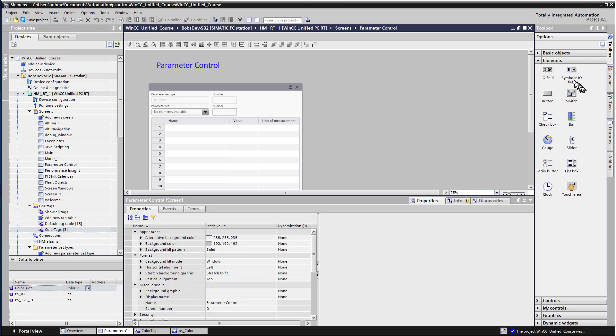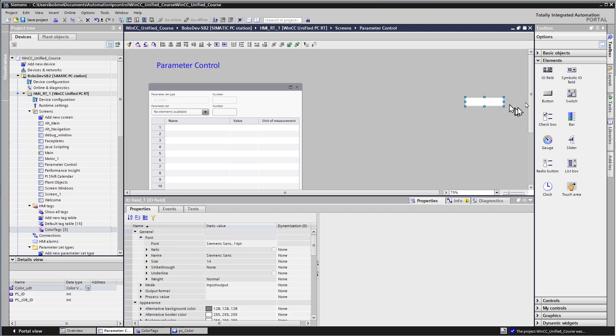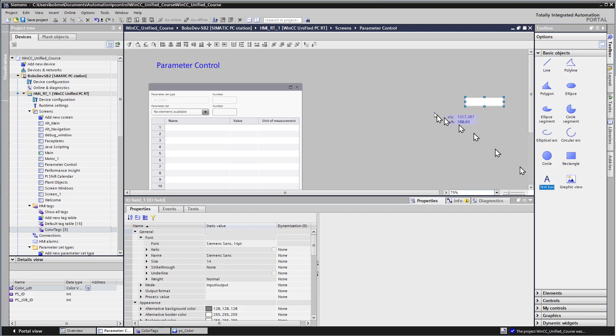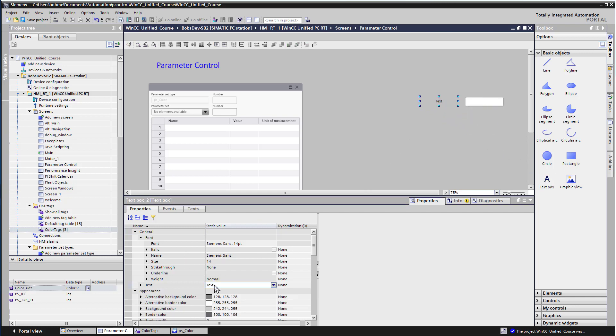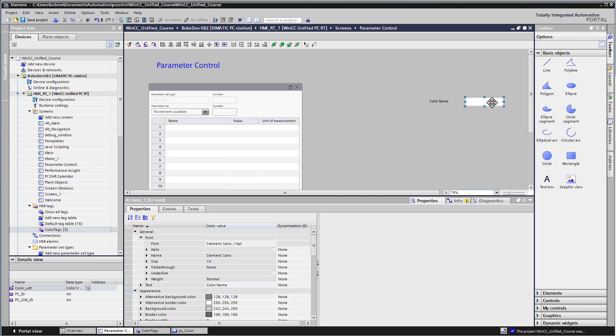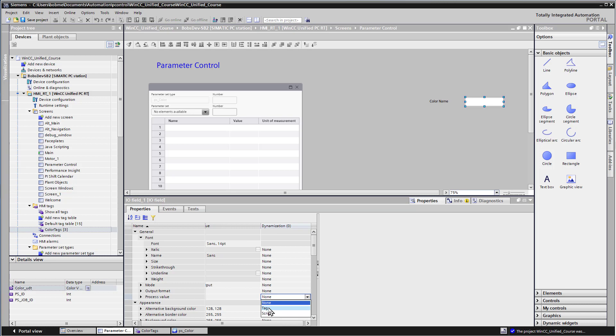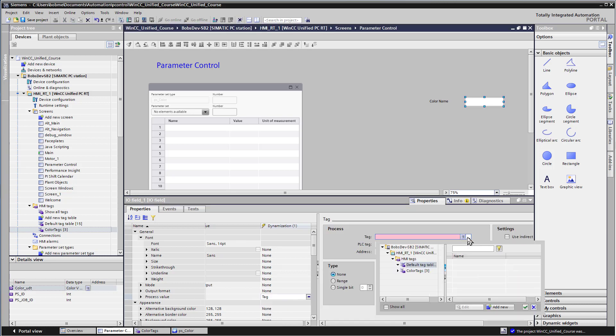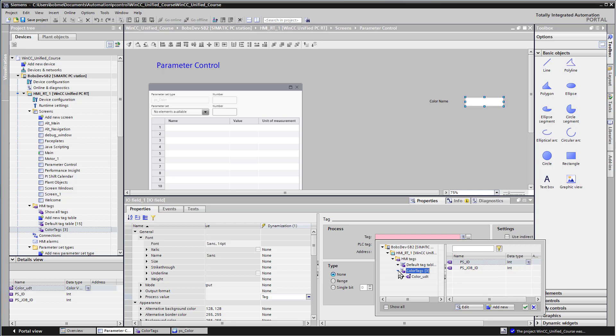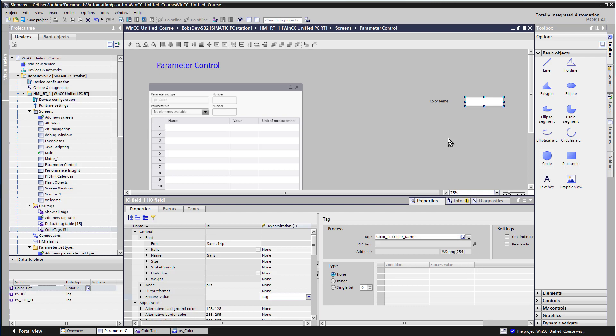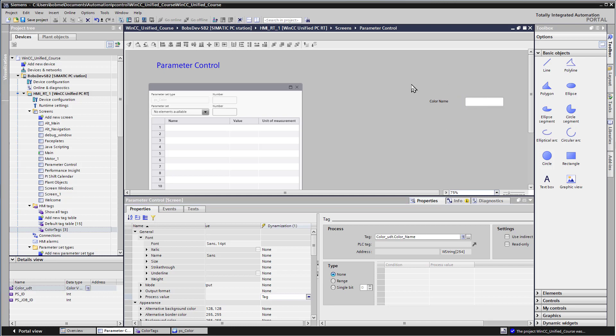We'll go to elements and add an IO field. Then under basic objects, we'll add a label. For our label, the first element is color name. On the IO field, under process value, we'll do the dropdown under dynamization and choose tag. We'll go to our color tags table and expand it. Here are the elements of our UDT, and we'll just assign color name. Then we're just going to copy these and assign the rest of the elements.